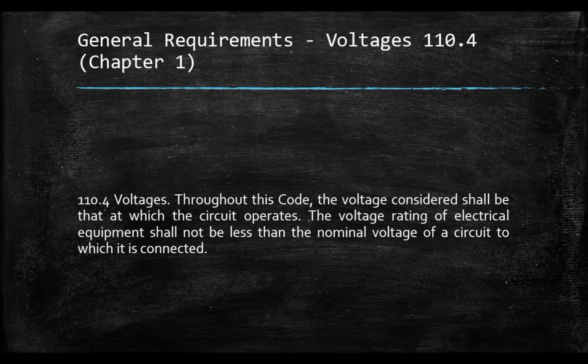The voltage rating of electrical equipment shall not be less than the nominal voltage of a circuit to which it is connected. Sinasabi dito na as defined in Article 100, nominal voltage is a nominal value assigned to a circuit or system for the purpose of conveniently designating its voltage class. For example, 120/240 volts, 480Y/277 volts, and 600 volts.